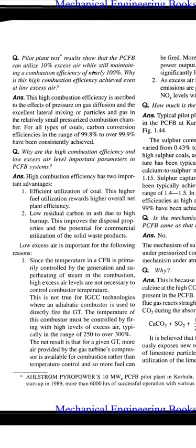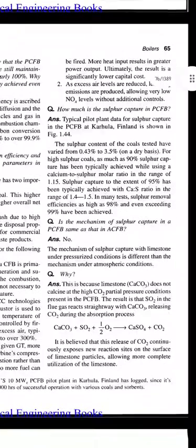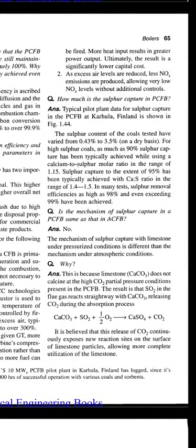The temperature of the combustor must be controlled by firing with high levels of excess air, typically in the range of 250 to over 300%. The net result is that for a given gas turbine, more air provided by the gas turbine's compressor is available for combustion rather than for temperature control, and so more fuel can be fired. More heat input results in greater power output, and ultimately the result is a significantly lower capital cost.